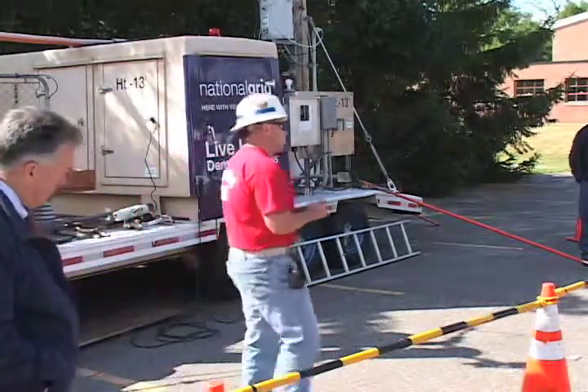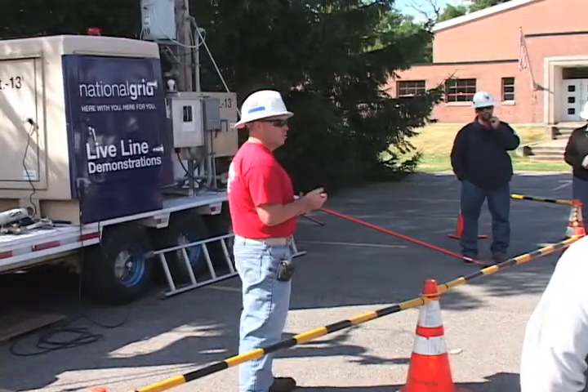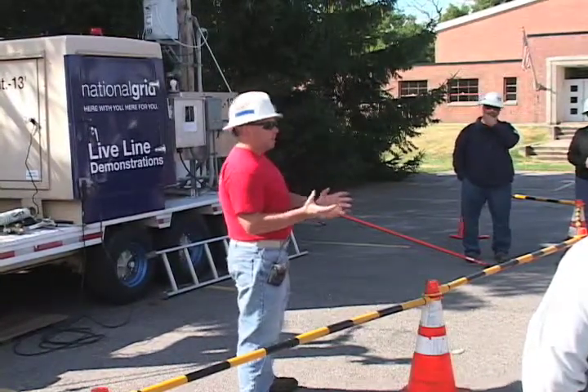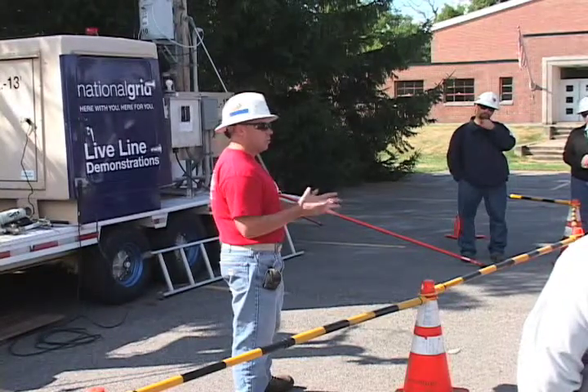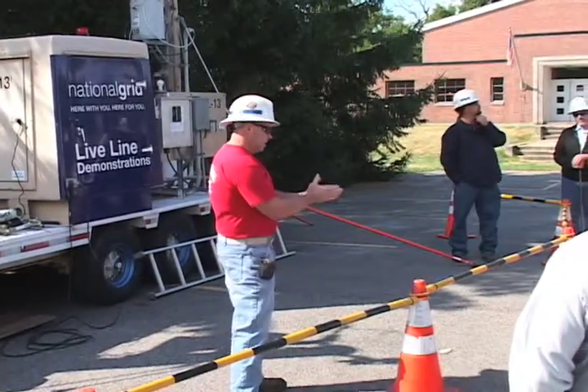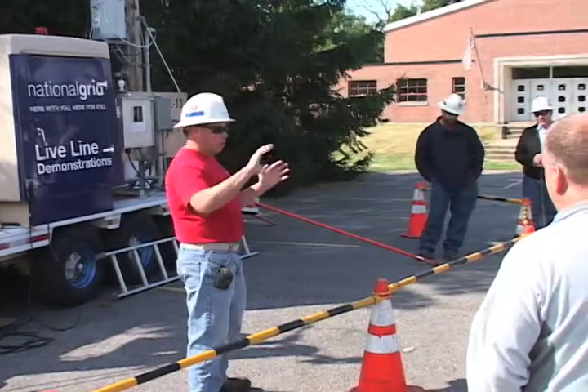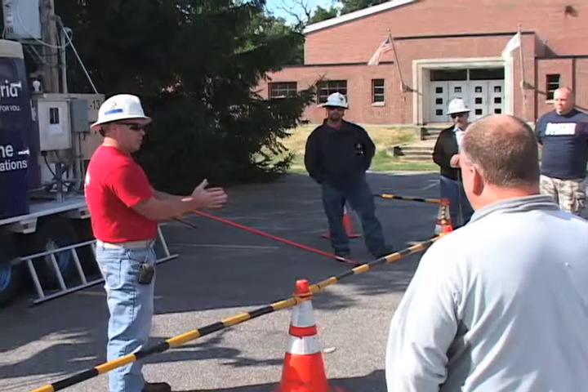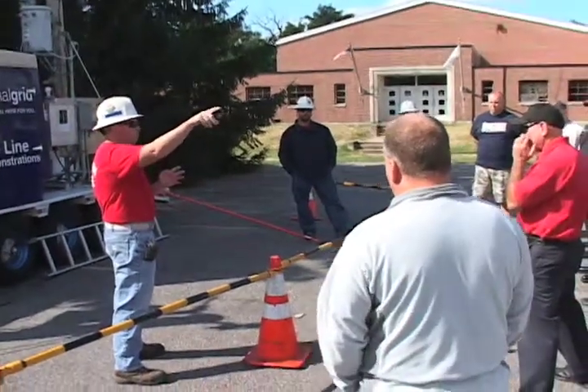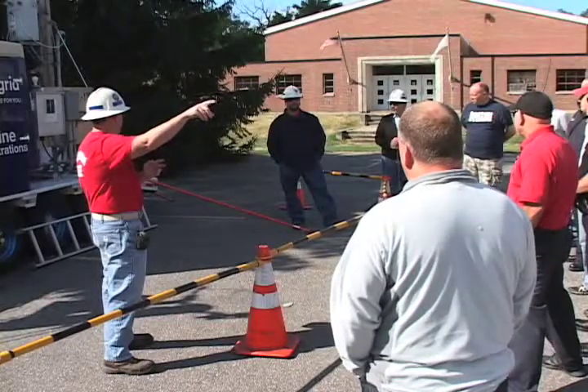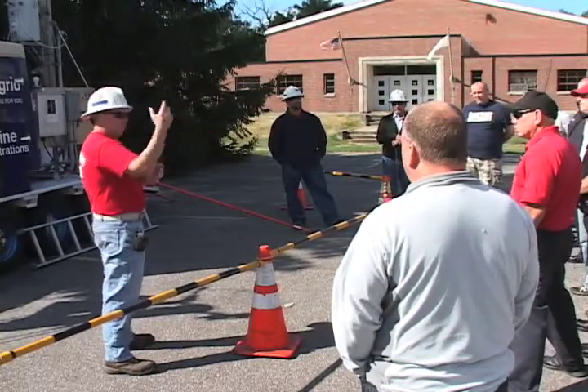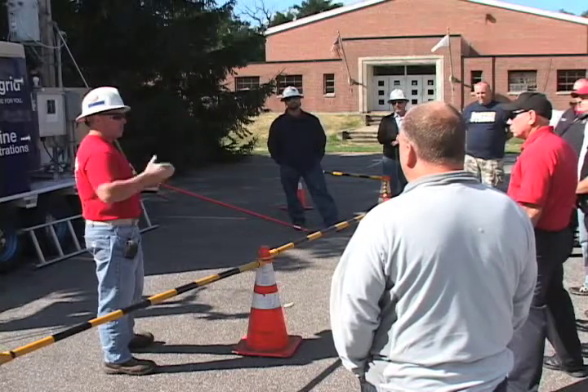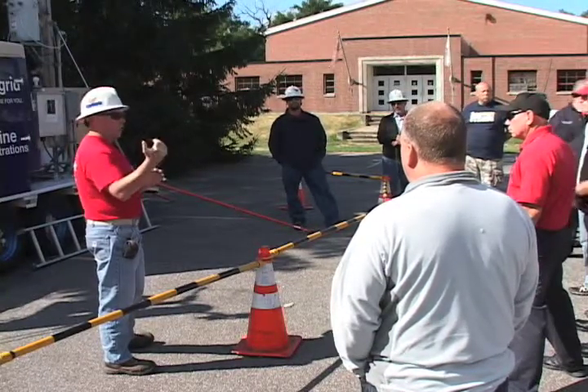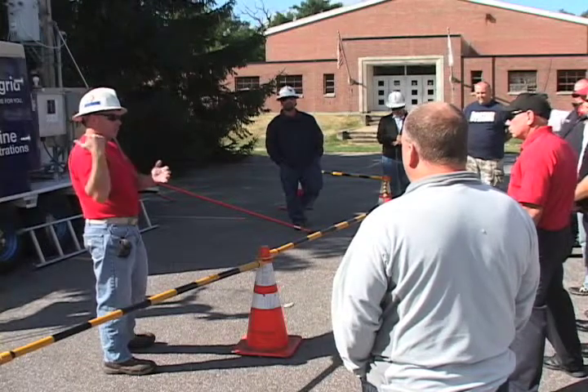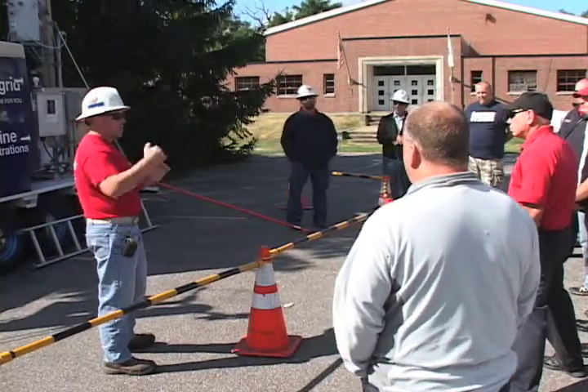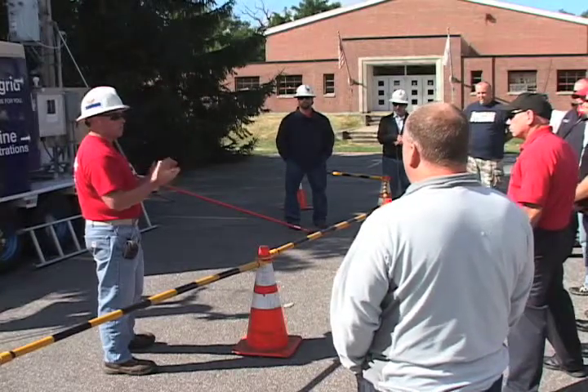What we have out on the lines are called reclosers. From a reliability standpoint, engineering determines where to put them. Instead of losing a whole feeder line, they place a recloser at a certain point. There's one right up on Rainer Ave by the rotary, at the end of Essex Street, and it feeds down this way. If there's a problem, say a tree branch causing a fault, the recloser will see that fault and open up. Everything from that recloser outward will be de-energized, but everything from the substation to that recloser will remain energized.